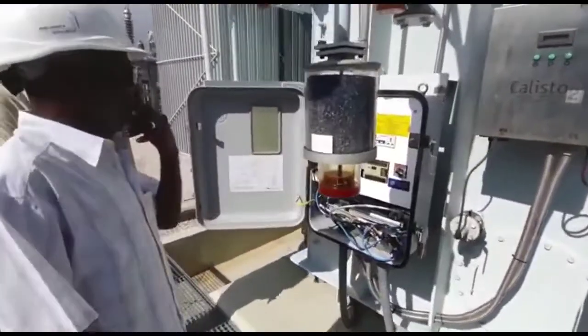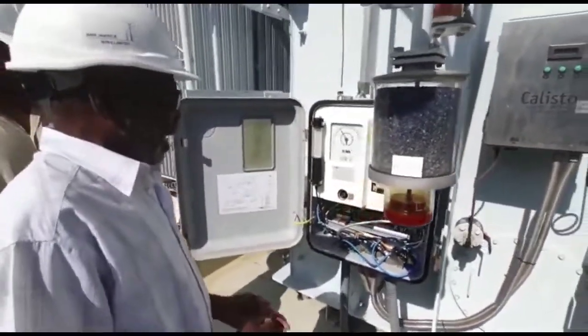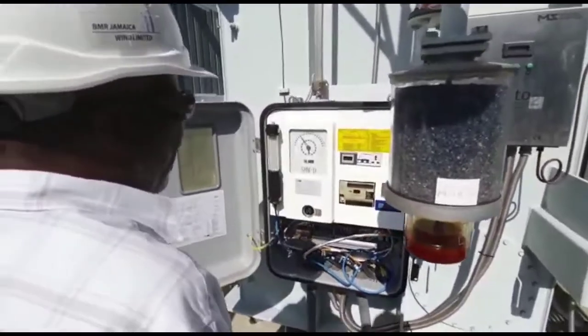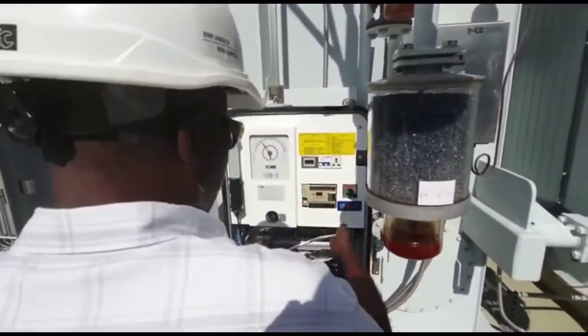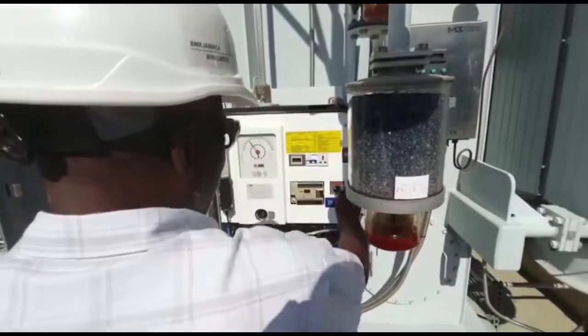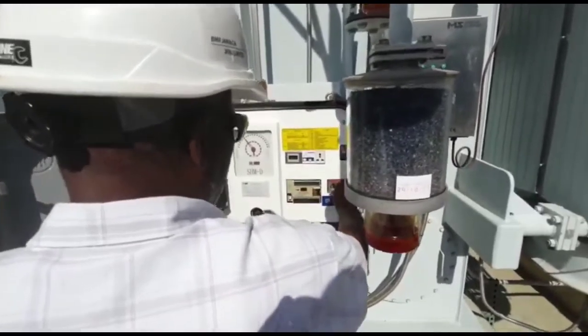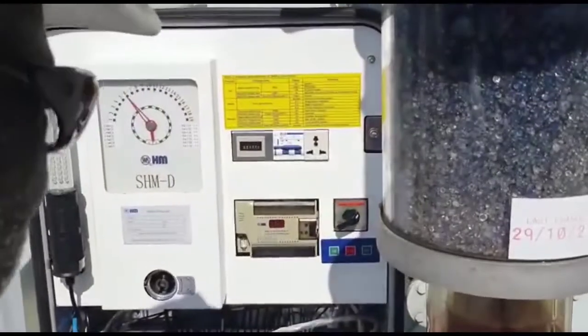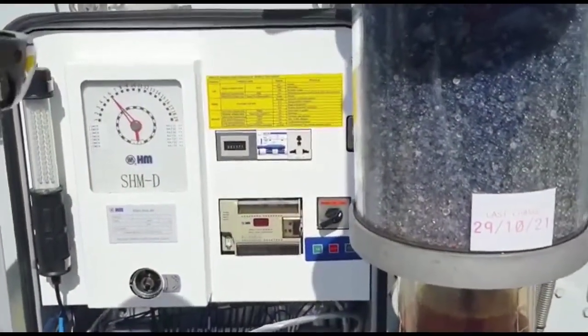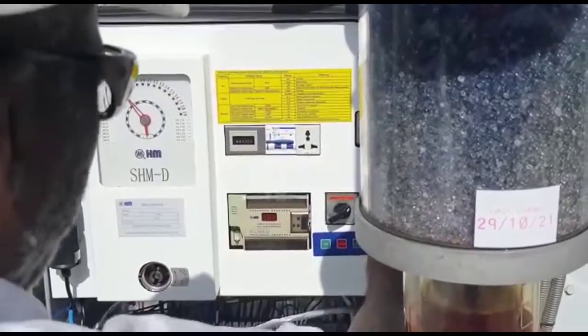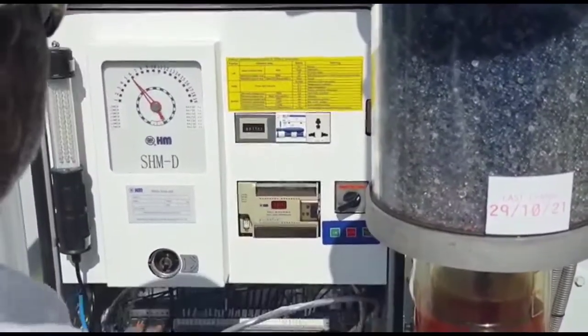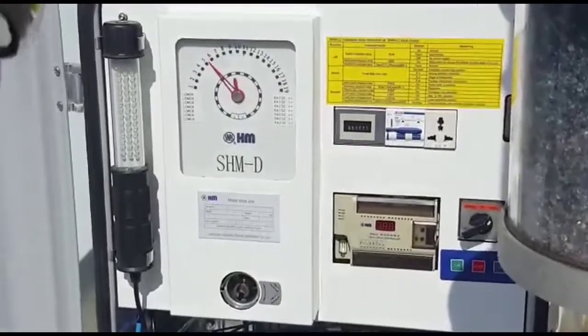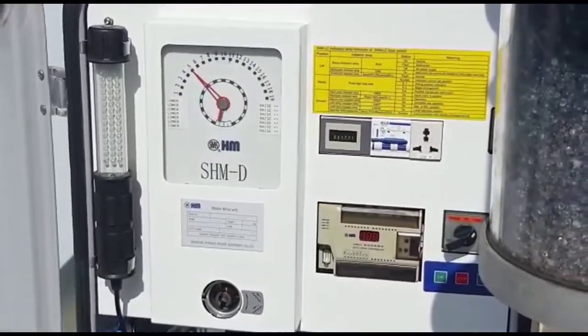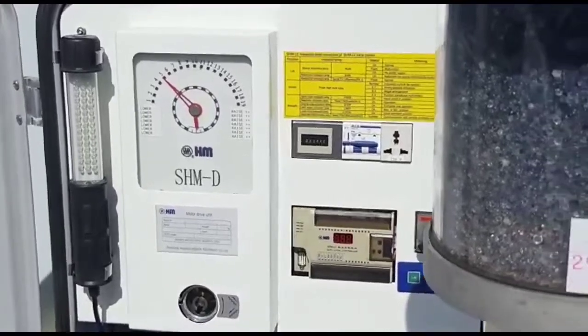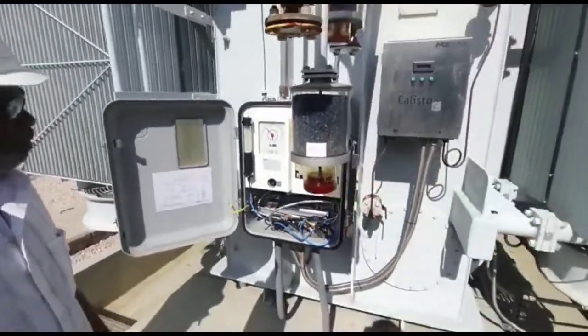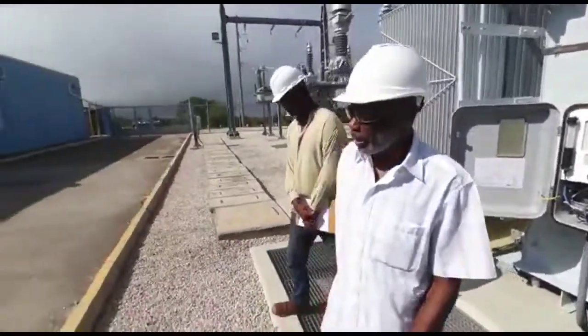This is now the tap changer mechanism, and right now it's in remote, and the voltage is still high, so we need to cut down a little more. So how to operate this: we put this to local, and we want to lower the voltage some more. So we press here. And the voltage should be lower than what it was before. We go inside and take a look to see what's going on.